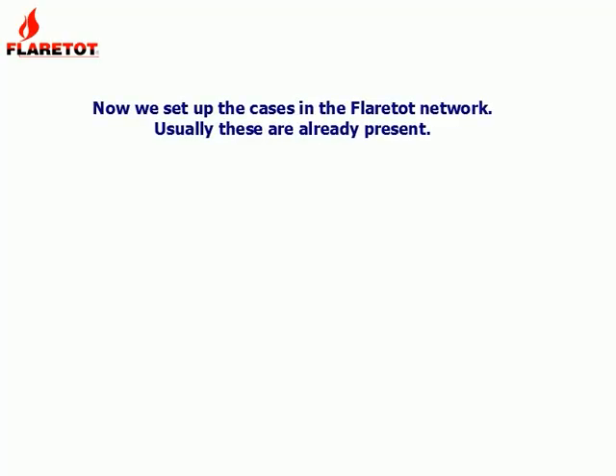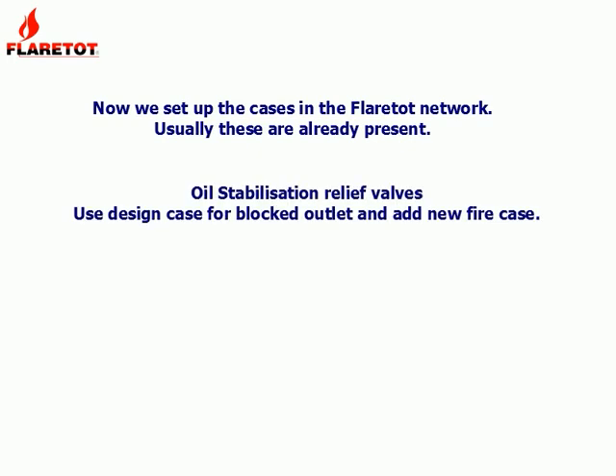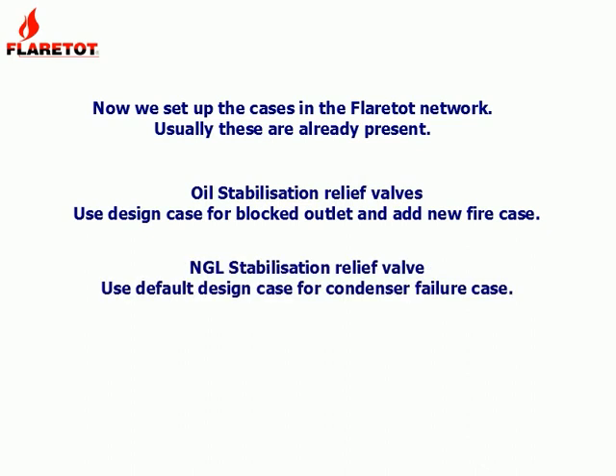Now we set up the cases in the flaretot network, so we can import the stream data. This only needs to be done once. If PetroSim data is revised, data can be imported again. The oil stabilization relief valves each require a new fire case. The default design case can be used for the blocked outlet. The NGL stabilization relief valve condenser failure case can use the default design case.